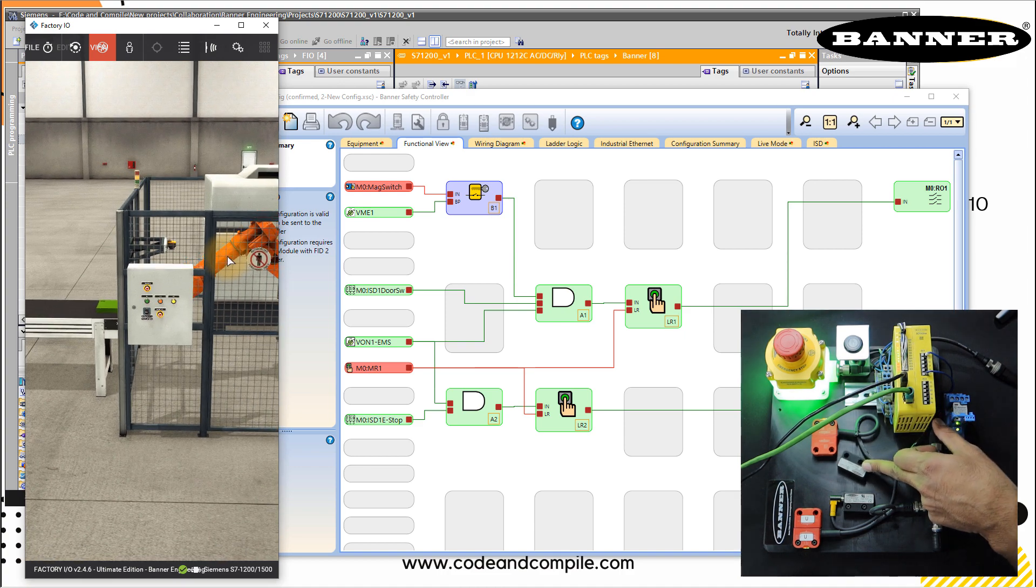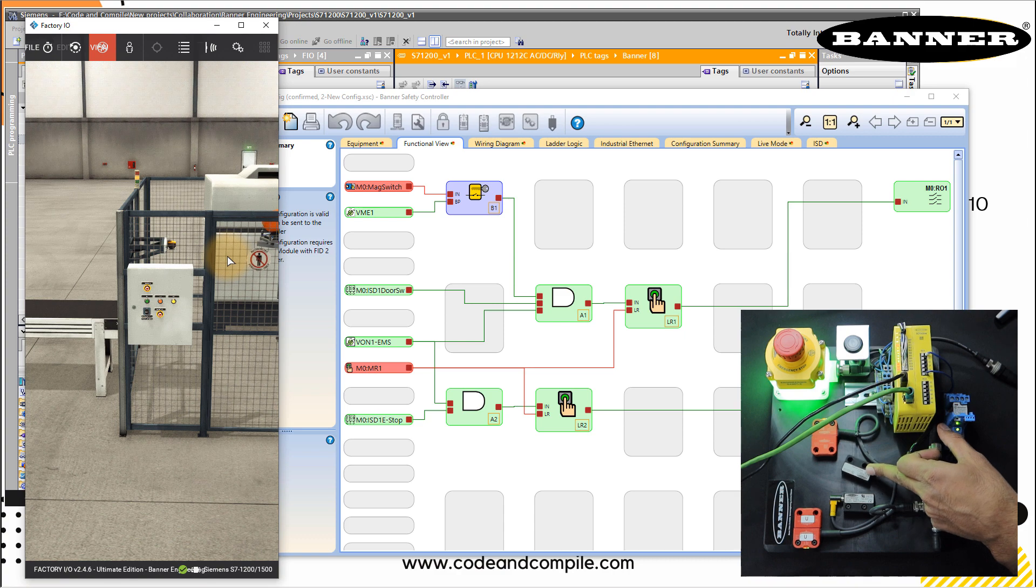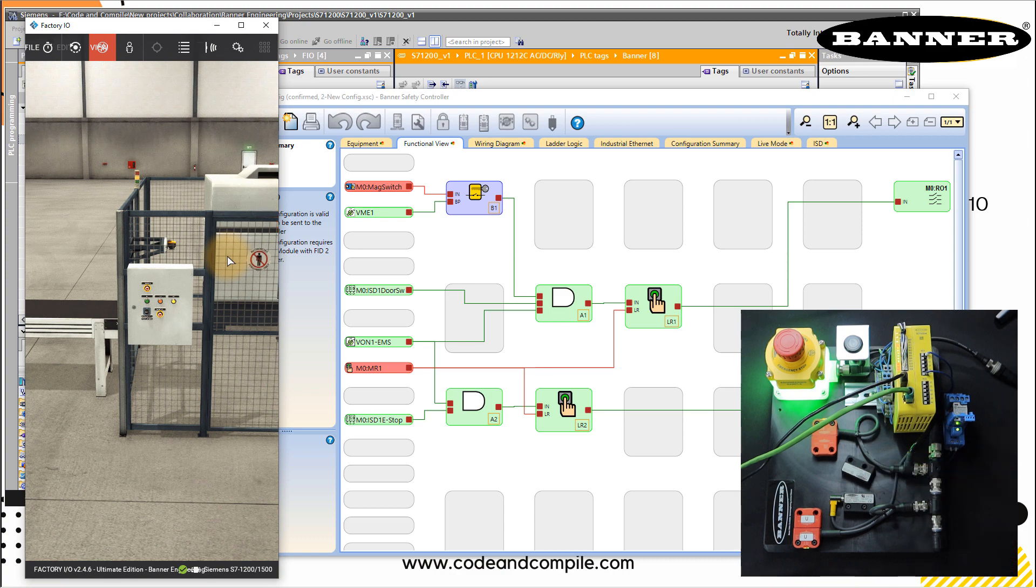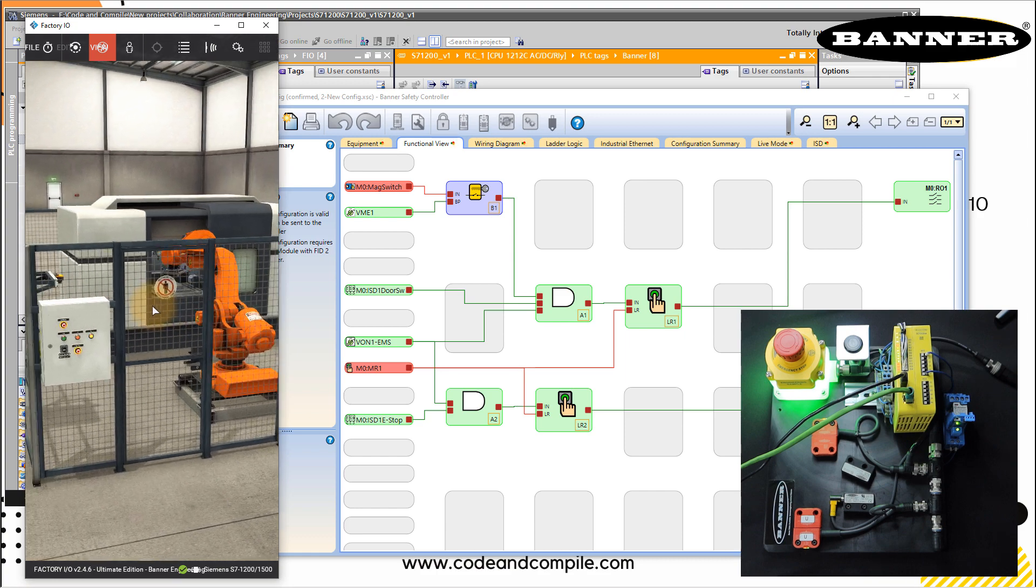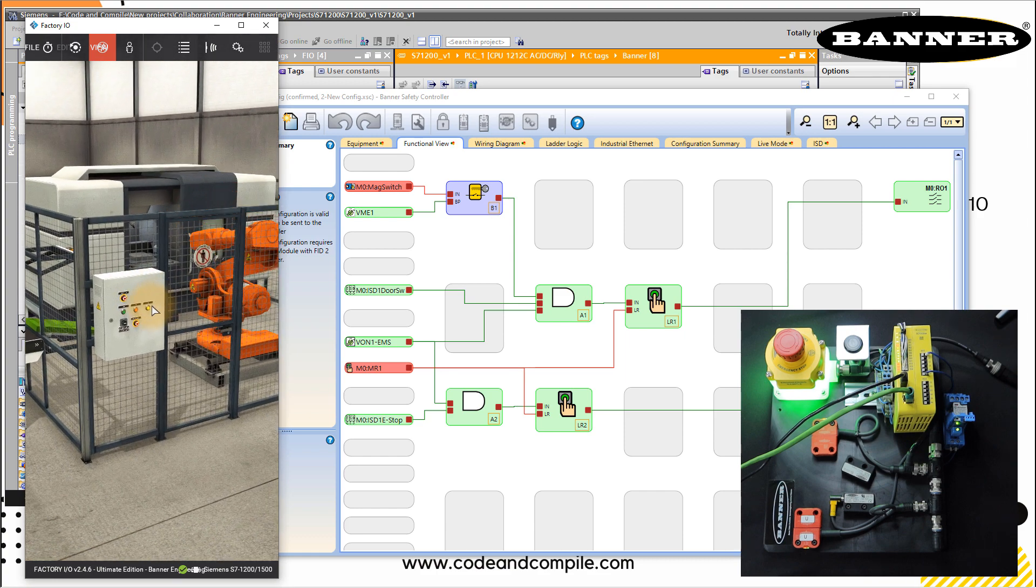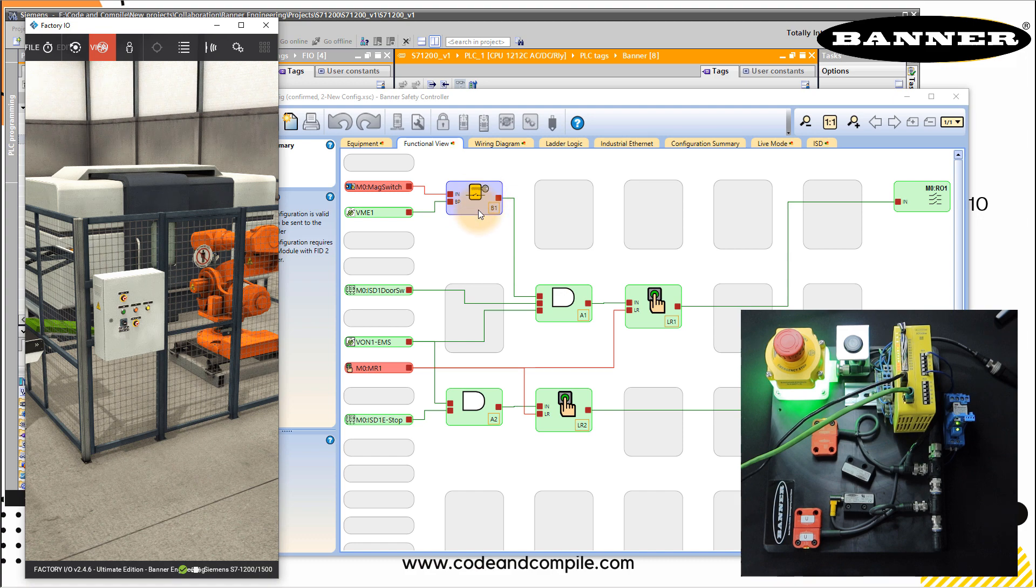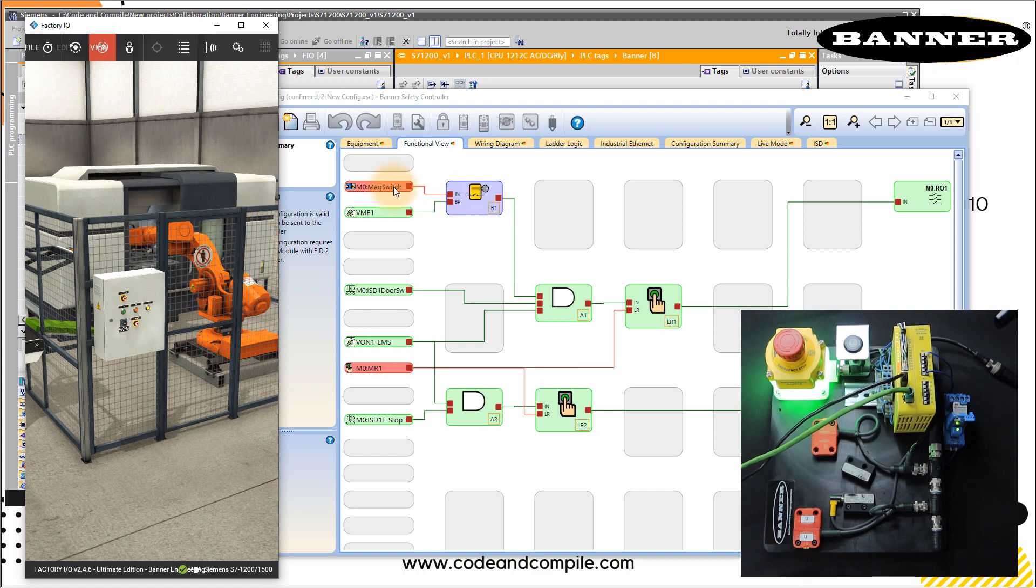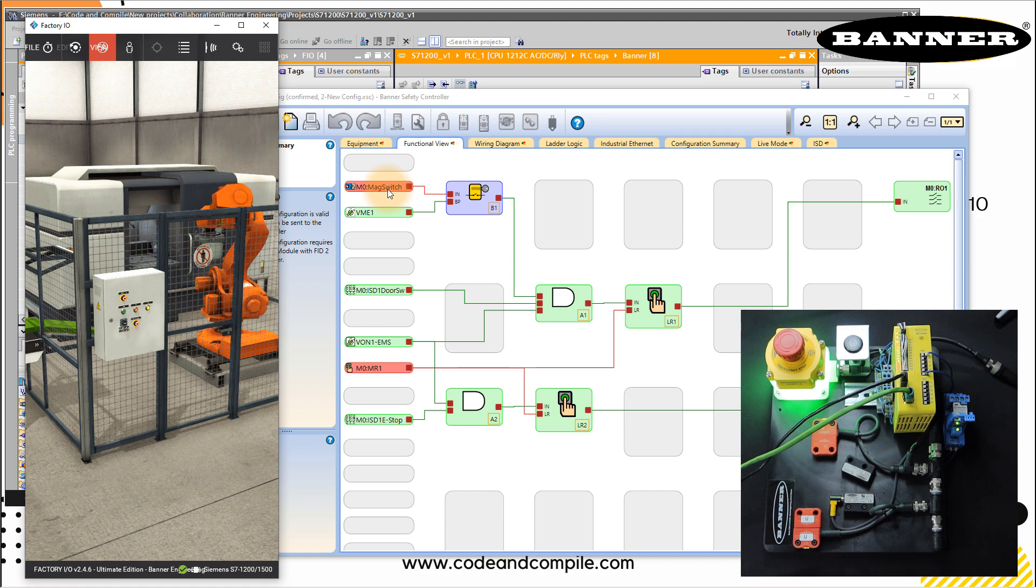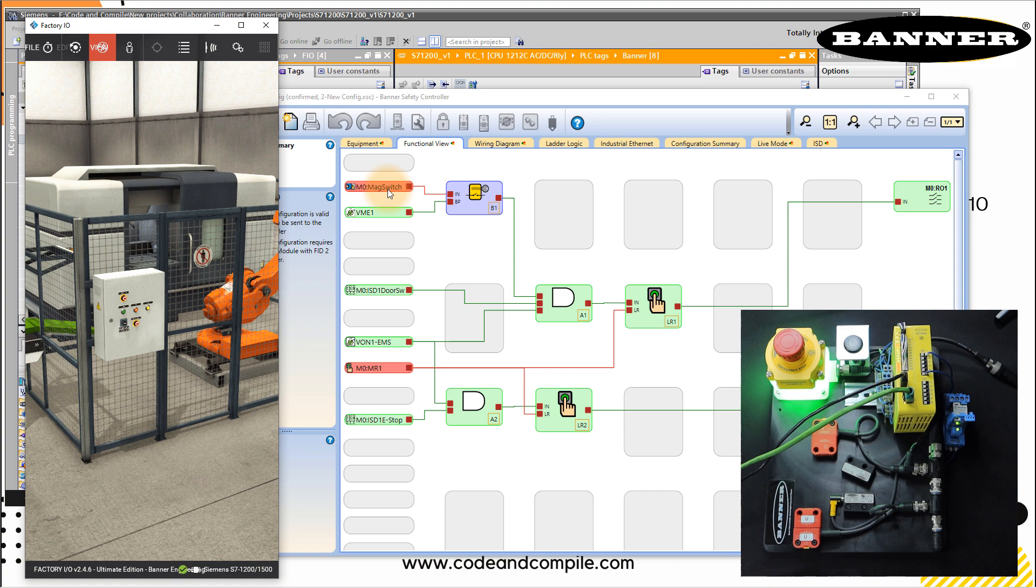Now this switch is out of my safety circuit, and my operation is working. But this will only work until one minute. This was the limit which we set. So we wait for a minute. And we will notice this will stop bypassing and then it will look for the switch to be active again. So we just wait one minute, I can maybe fast forward this video until it gets active again.